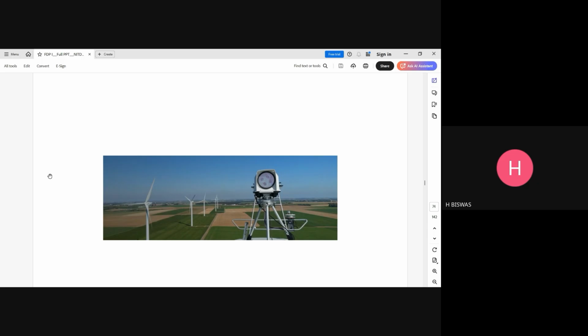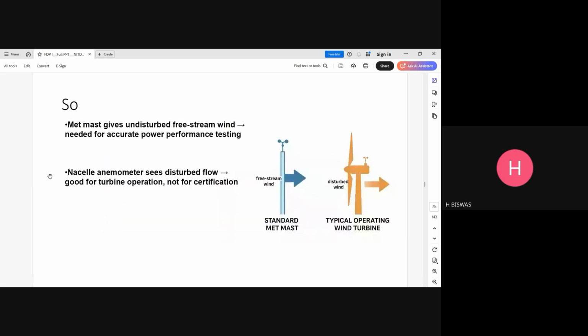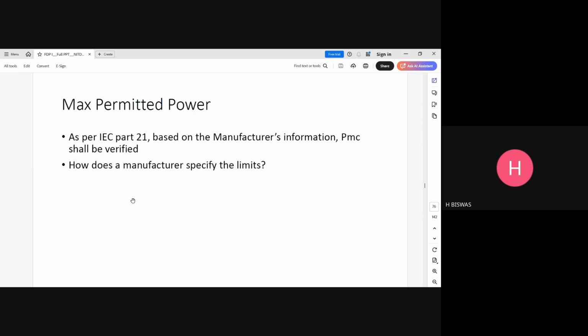So here it is a LiDAR-based wind speed recording mechanism. If you see this LiDAR data, it tends to capture the wind speed in different forms. But of course, the site is in onshore wind speed, and that it gives. So, in general, Met mast gives you the undisturbed free stream wind needed for accurate power performance testing, and a nacelle anemometer sees disturbed flow, good for turbine operation, not for certification.